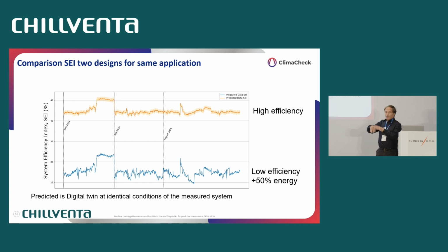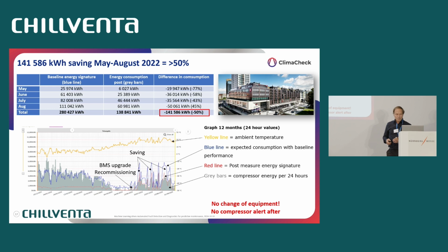And if we look at total system efficiency, this is two different chillers sold on the same specification, but this is how they actually operate. You get a little bit surprised, I mean, this is a 50% difference in energy consumption on two new sites sold on the same specification. Like, what? So this needs to receive much more focus.